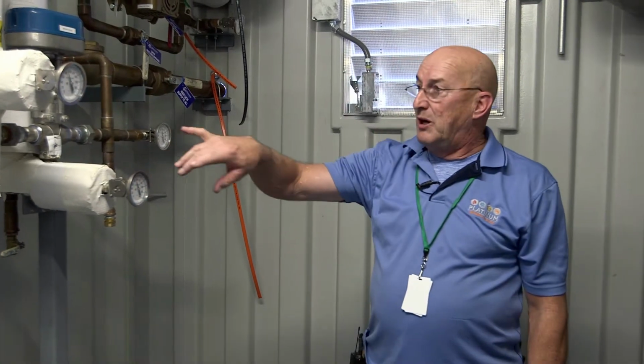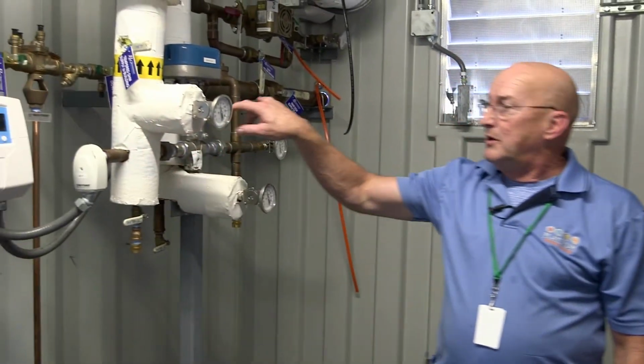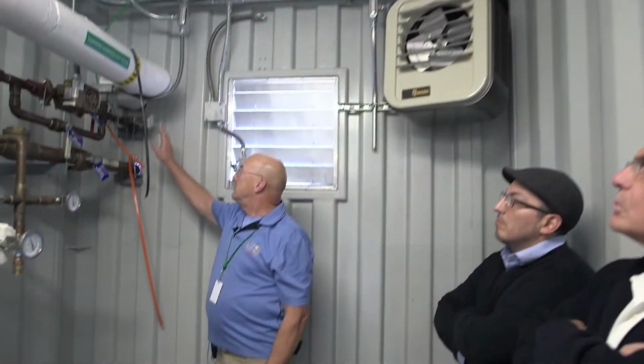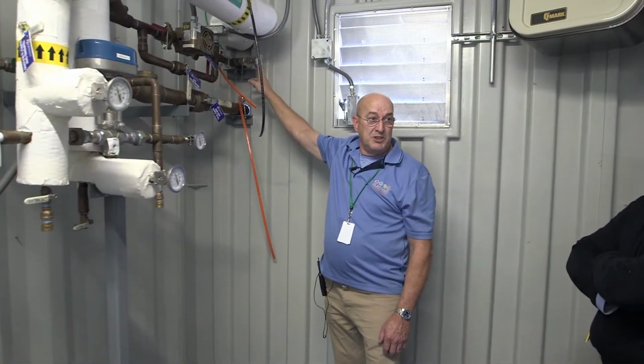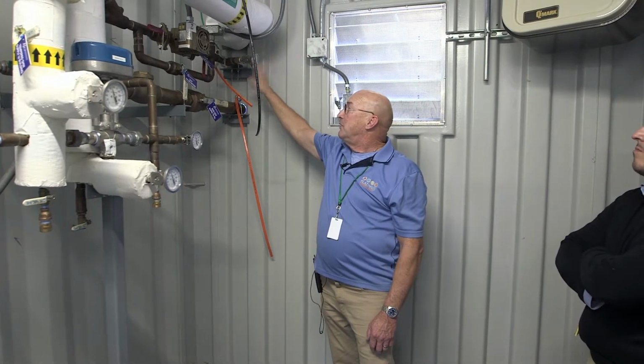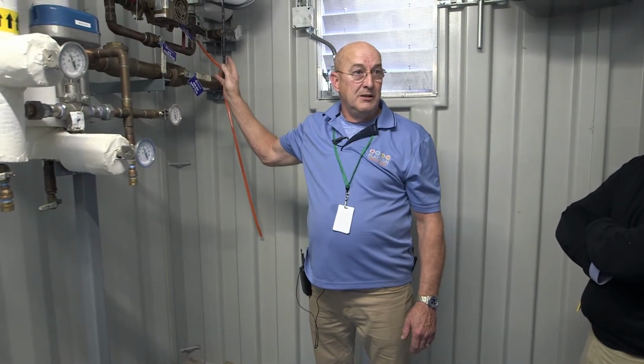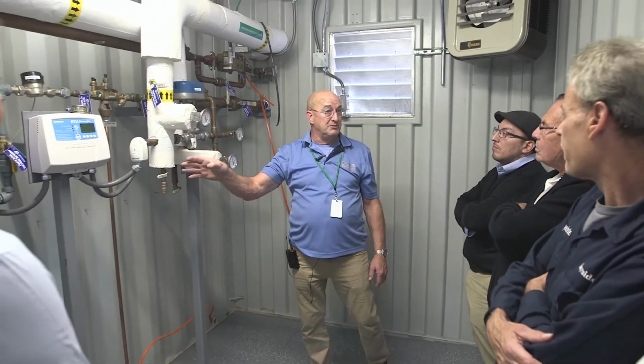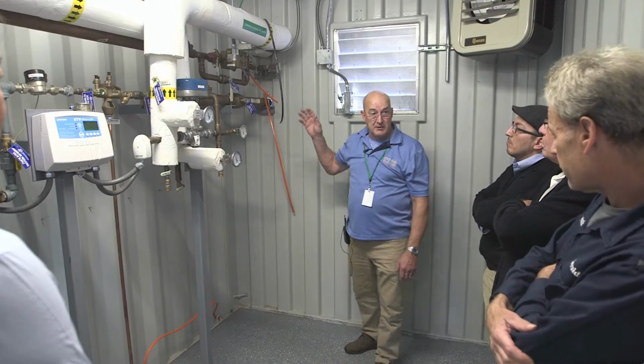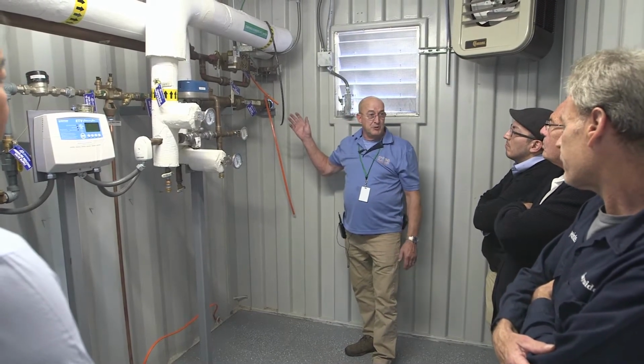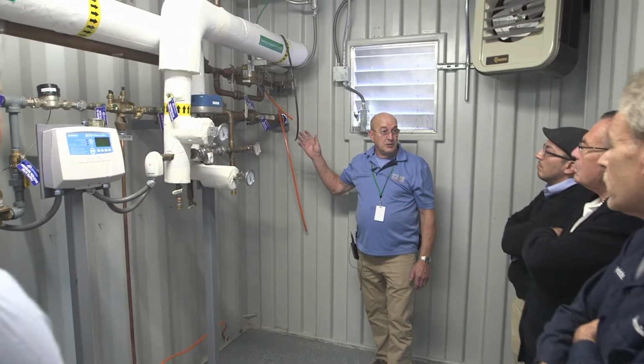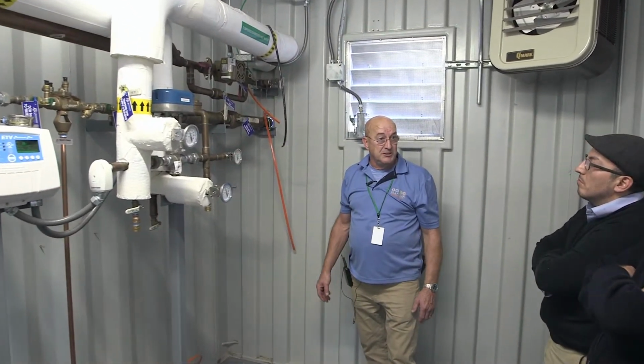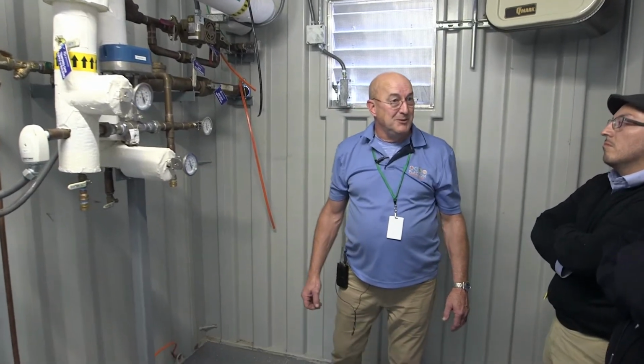You have all your thermometers to tell you what it is. These are the sensors for it, that feed information to here. So this is your recirc line. You've got a thermometer here. It'll tell you what temperature the recirc line's coming back. Very important, because you'll know if you have a problem with faucets mixing somewhere in the building, cold water getting in. The temperature coming back is going to average anywhere between 100 and 120, what the mixing valve is set at. If it's not in between there and it's down at like 70 or 80 degrees, you've got a problem somewhere in the building. There's cold water getting into the hot water line. Usually a sign of either a faucet going bad that it's mixing, or somebody hooked up a washing machine somewhere. We know the routine.